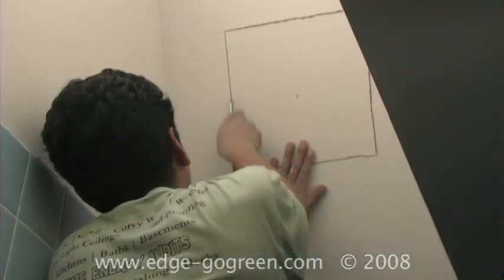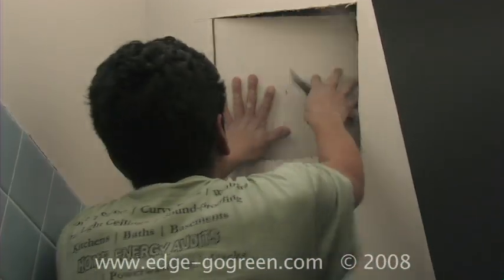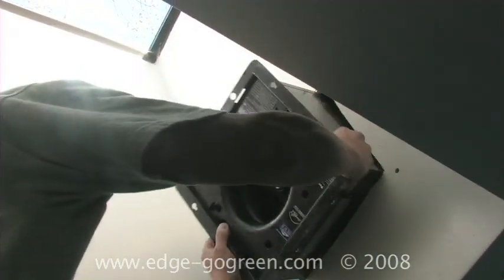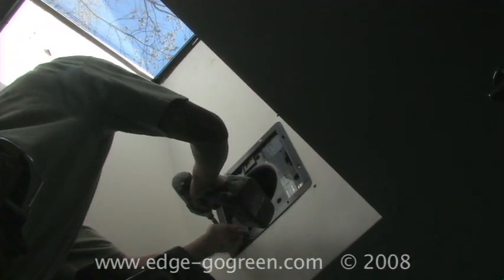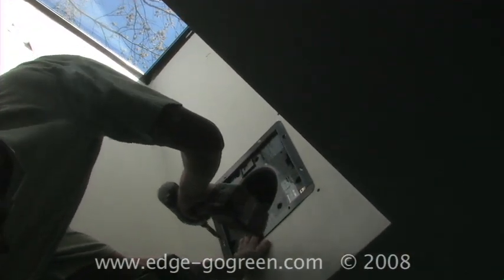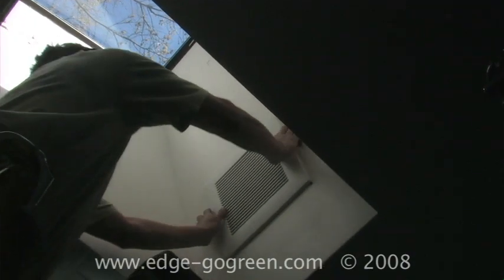Now, in this room also we ran into a couple of other issues with ventilation in the sense that we did not even have a bathroom fan installed. So what we've done in retrofit is to actually install one into the skylight shaft. And there's a design issue here that made this a little bit trickier of a job, mainly because they installed initially a skylight shaft directly above the shower stall. And the shower itself is creating a warm, humid, moist air, which is less dense than cold air, and it's rising up into the skylight shaft.